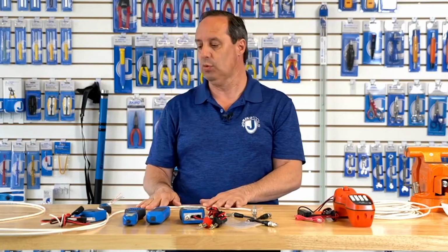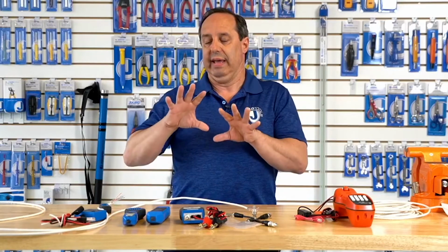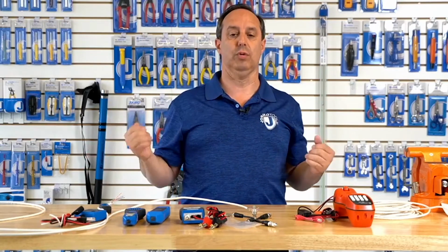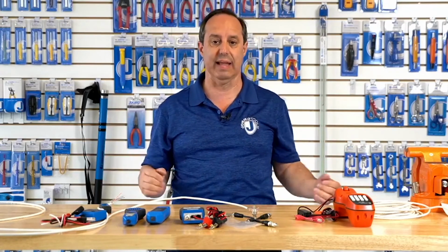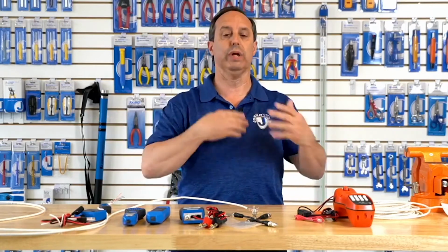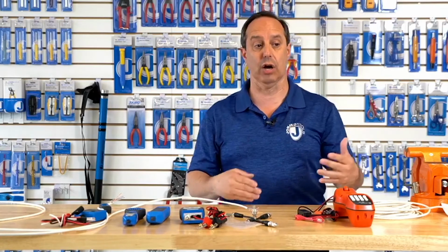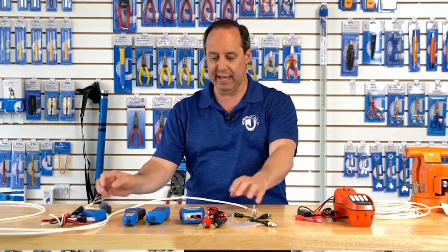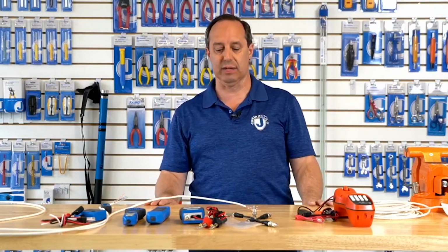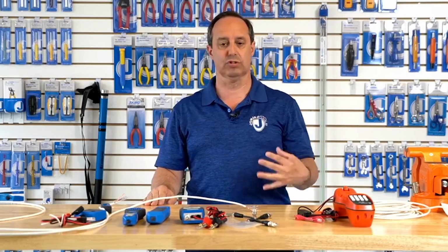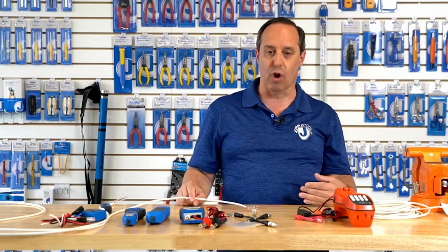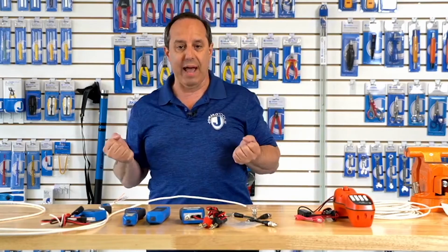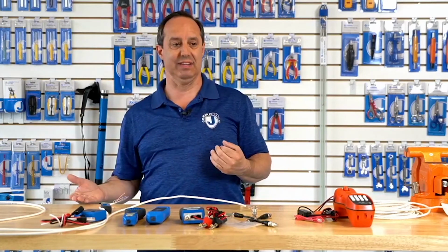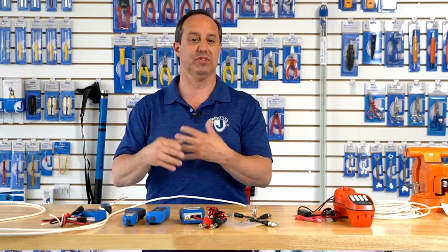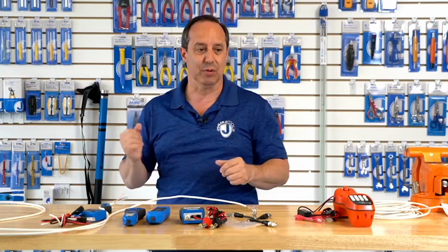One thing you want to do is make sure, in a cable bundle, to isolate that cable as best you can, because you will get crosstalk. It can occur, so you want to back away and get that cable as isolated as possible. If you're getting crosstalk in a cable bundle, look for the cable with the strongest signal, pull that one out further, and check it again to make sure it wasn't a false positive.